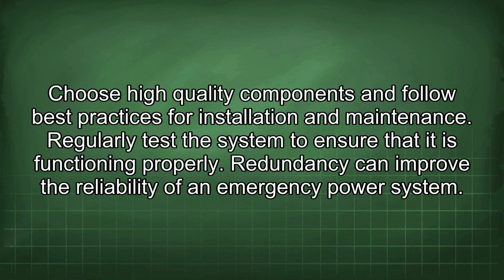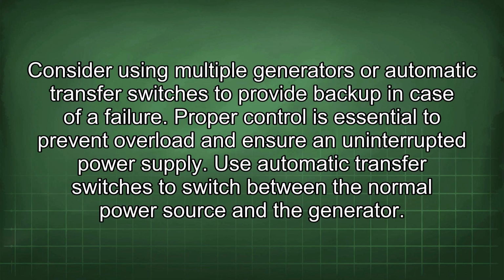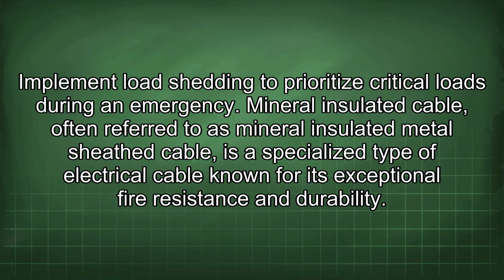Redundancy can improve the reliability of an emergency power system. Consider using multiple generators or automatic transfer switches to provide backup in case of a failure. Proper control is essential to prevent overload and ensure an uninterrupted power supply. Use automatic transfer switches to switch between the normal power source and the generator. Implement load shedding to prioritize critical loads during an emergency.